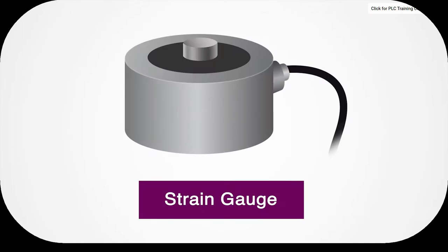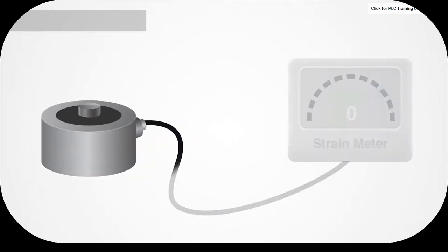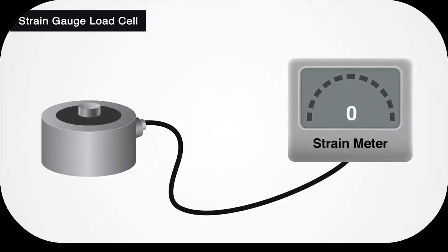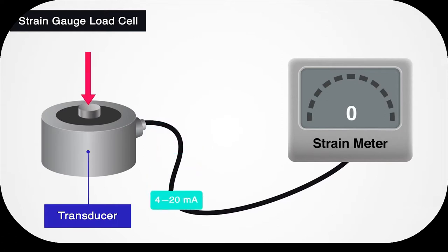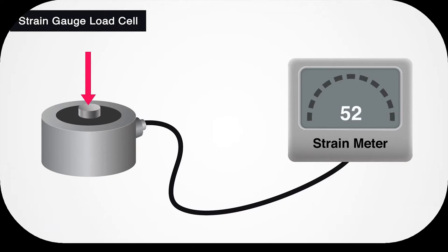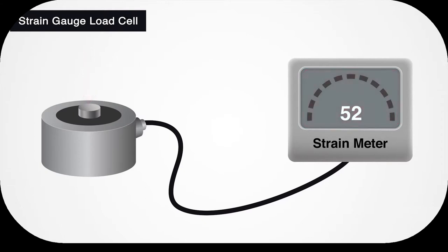The next type is the strain gauge load cell, which is the most popular style. A strain gauge load cell is a transducer that changes in electrical resistance when under stress or strain. The electrical resistance is proportional to the stress or strain placed on the cell, making it easy to calibrate into an accurate measurement. The electrical resistance from the strain gauge is linear and can be converted into a force and then a weight.